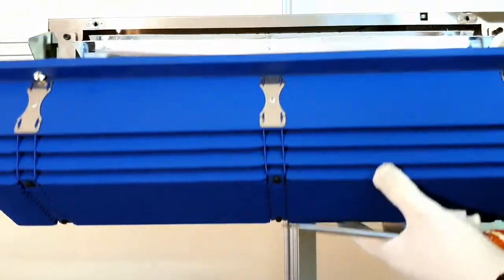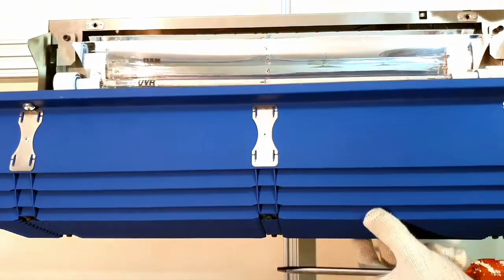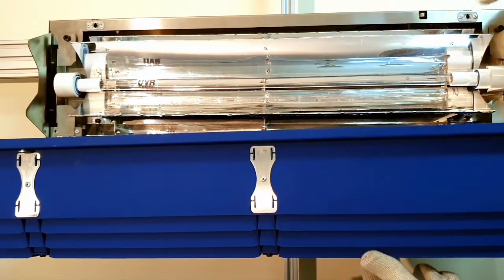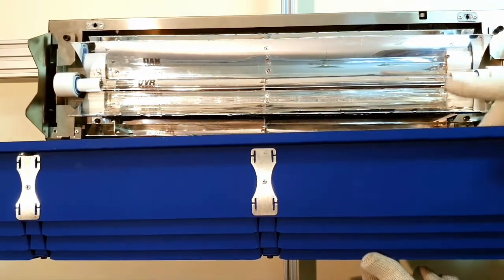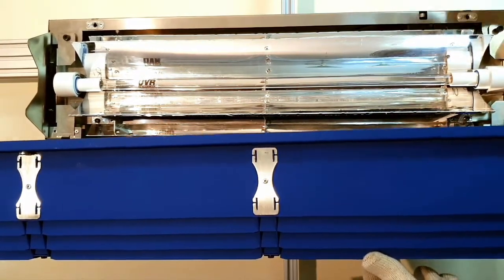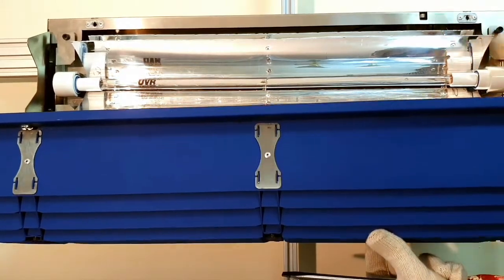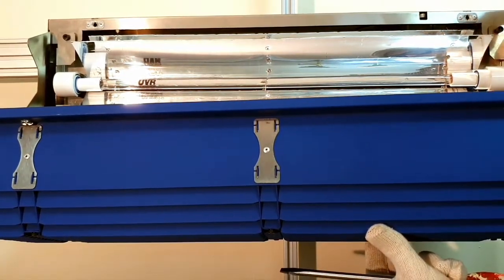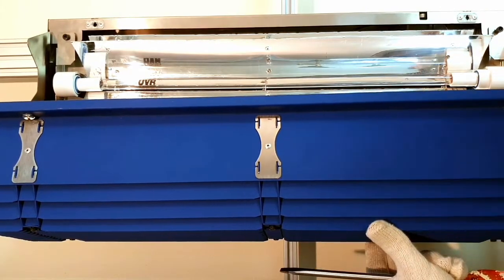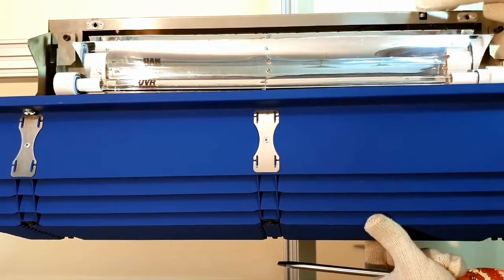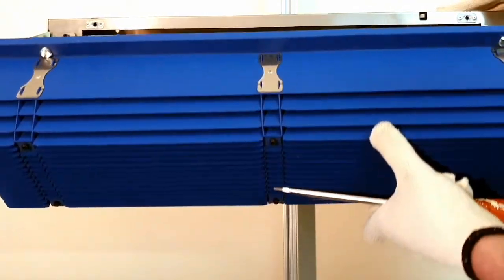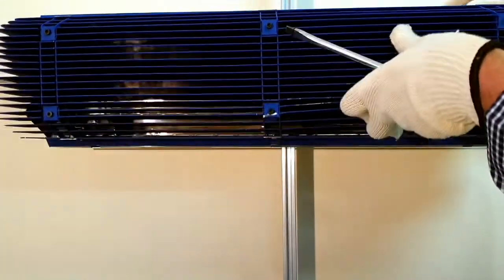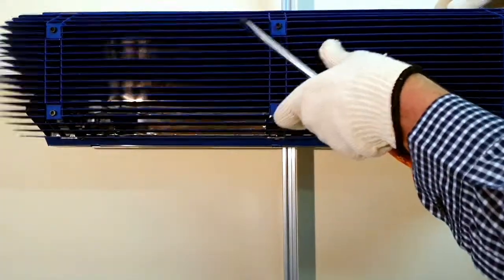Just a note, some of these units have safety switches, like this unit. There's a safety switch over here, and if your lamp face isn't closed properly, the lamps won't switch on again, the device won't switch on again. If that happens, it might give you the false impression that there's something wrong with the lamp. So just watch for those switches that they make properly when you close the device.